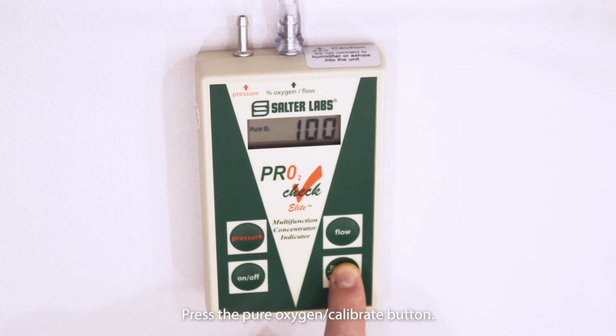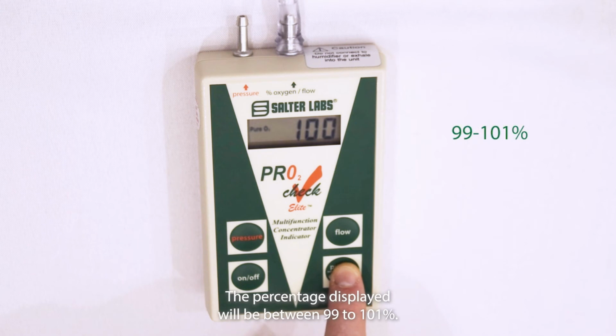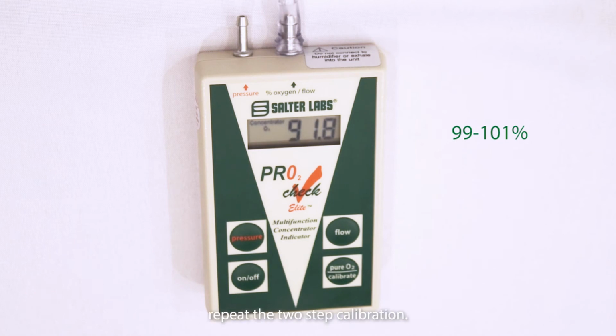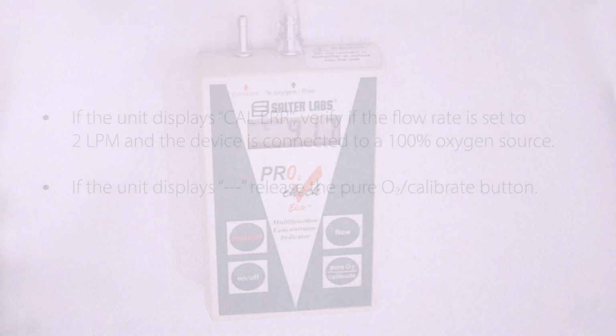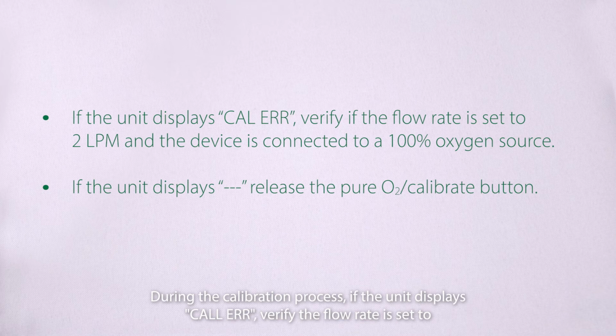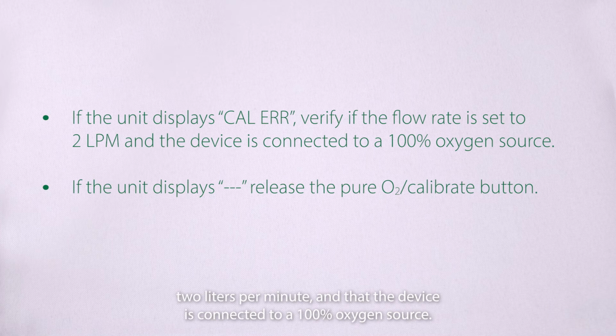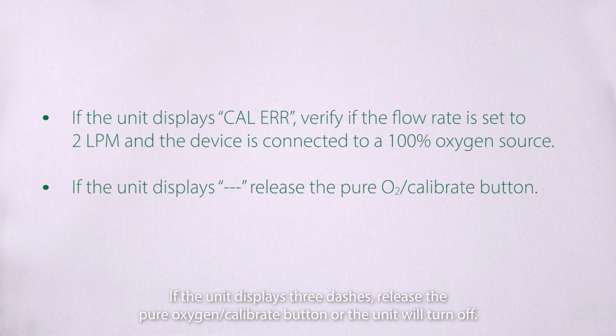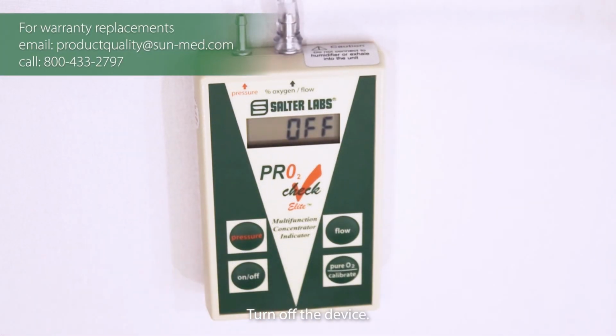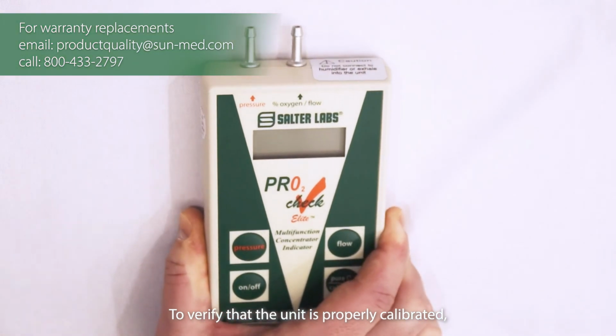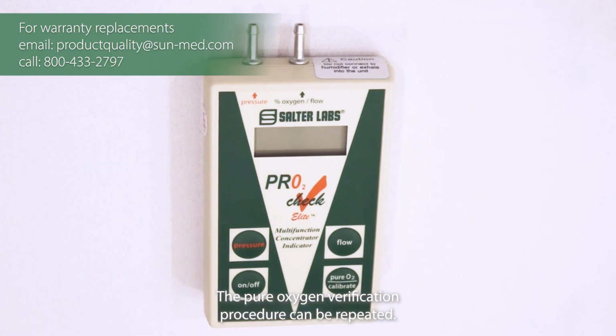Press the Pure Oxygen Calibrate button. The percentage displayed will be between 99 to 101%. If the reading is out of range, repeat the two-step calibration. During the calibration process, if the unit displays CAL ERR, verify the flow rate is set to 2 liters per minute and that the device is connected to a 100% oxygen source. If the unit displays 3 dashes, release the Pure Oxygen Calibrate button or the unit will turn off. Turn off the device. To verify that the unit is properly calibrated, the Pure Oxygen verification procedure can be repeated.